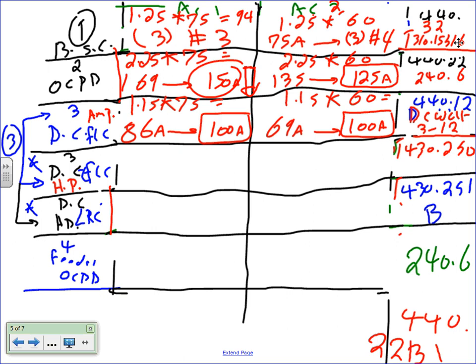The horsepower, you go to two locations. One is full load amp. Believe it or not, this is a full load amp. So you're going to size two things based on, I hate it when it becomes full load amp, okay? And the second one is locked rotor current. Very easy. I just want to remind you, you're going to go to table 430.250 and 430.251 for each one of them. Look how they do it, guys.